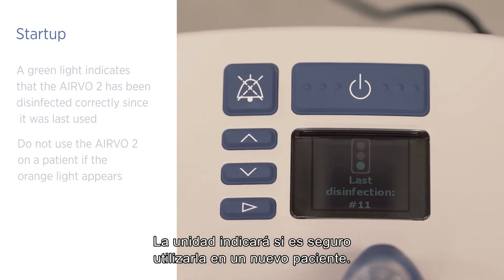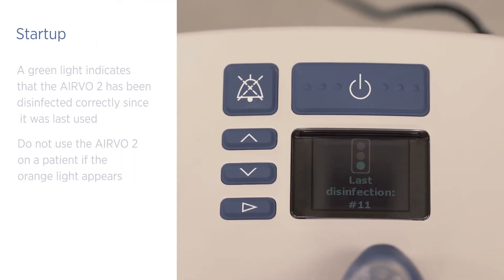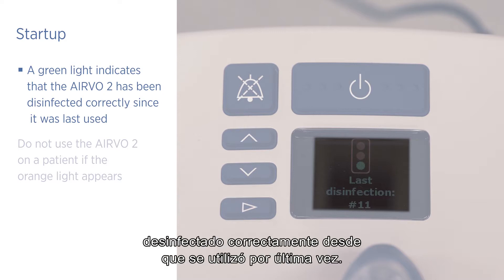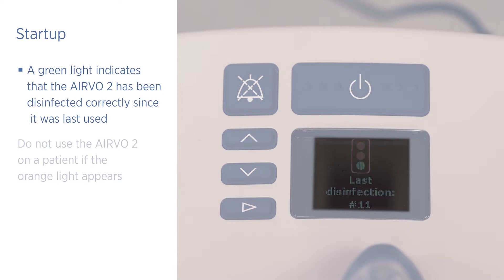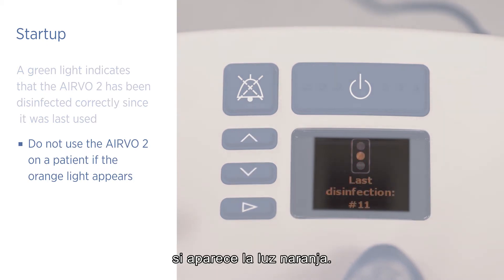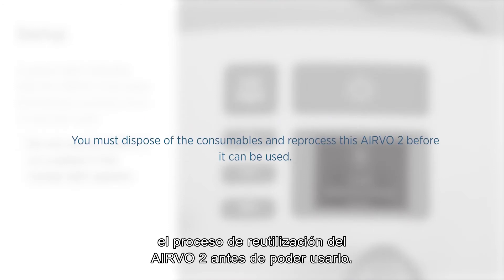The unit will show you whether it is safe for use on a new patient. A green light indicates that the AIRVO 2 has been disinfected correctly since it was last used. However, do not use the AIRVO 2 on a patient if the orange light appears. You must dispose of the consumables and reprocess this AIRVO 2 before it can be used.